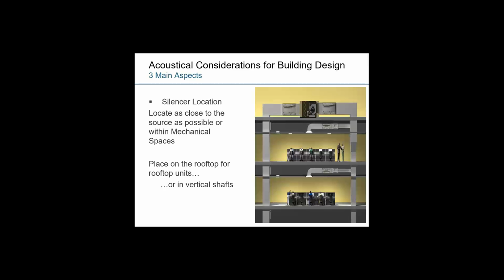If it's very close to a fan or an air handler or a terminal unit, the overall operation of these devices, you need to make sure that they're going to work accordingly. You don't want to cause system disruptions or increased pressure drop by maybe improperly locating something within a system. Attenuating the noise as close to the source as possible is also advisable because it prevents further transmission of that noise throughout the facility or the area in which you're concerned with.